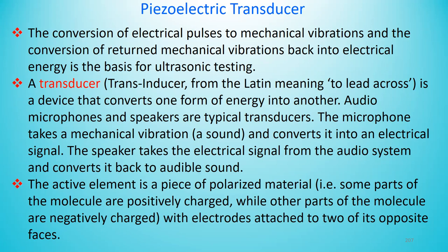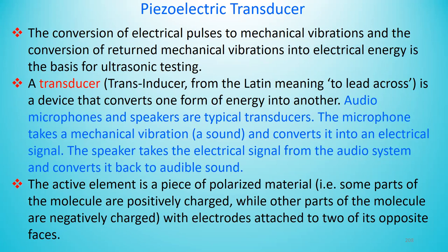The active element is a piece of polarized material, where some parts of the molecule are positively charged while other parts of the molecule are negatively charged, with electrodes attached to two of its opposite faces. The conversion of electrical pulses to mechanical vibration and the conversion of returned mechanical vibration into electrical energy is the basis of ultrasonic testing. So audio microphones and speakers are typical transducers.